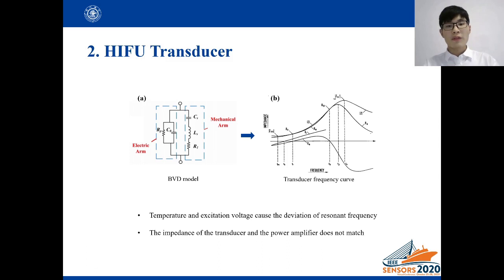The resonant frequency and impedance of the transducer determines its working state. But unfortunately, many factors will change these two important variables and cause mismatching between power amplifier and transducer in working.